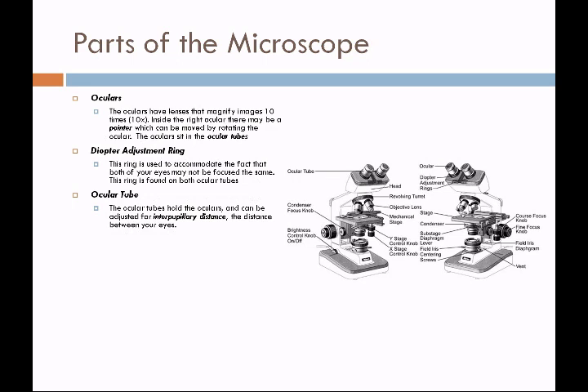The ocular tube houses the lenses and must be adjusted for interpupillary distance. Because this is a binocular microscope, everybody's distance between their eyes is a little different. I'll show you in lab how to adjust these so that you see a single image rather than two distinct images. The head is the top part of the microscope. It contains a delicate prism system which helps send an image to the oculars and your eyes. This image is actually going to be inverted.